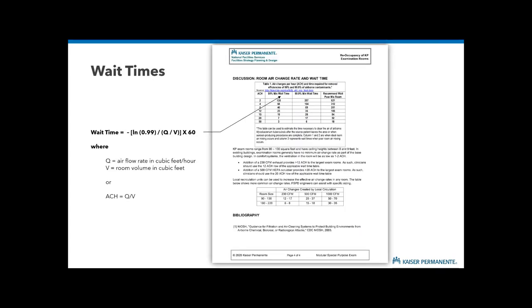It turns out that most of the conversation centers around this table. When you've had a suspect aerosol generating case in a room, this table ostensibly tells you how long you need to wait to get a 99% reduction in air contamination levels. I want to point out that this table is not rocket science, it's not actually science at all - it is, in fact, Algebra 2. The equation is right there on the screen. If you have a calculator with the natural log button on it, you can derive this table on the back of a napkin in 10 minutes. By the way, if you turn your iPhone sideways, your calculator now has a natural log button on it. If you have a spreadsheet, you can derive this table in 2 minutes. The basic principle is that if you have contaminated air in a room, you ventilate it with uncontaminated air and solve for how much time it takes to reduce those concentrations.